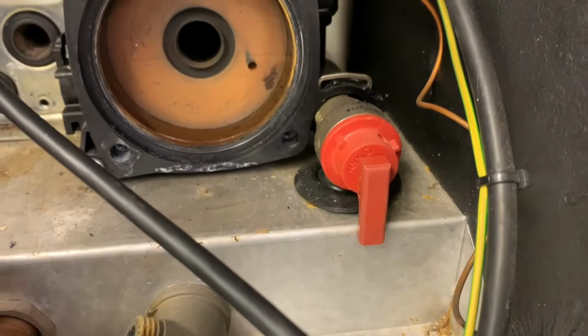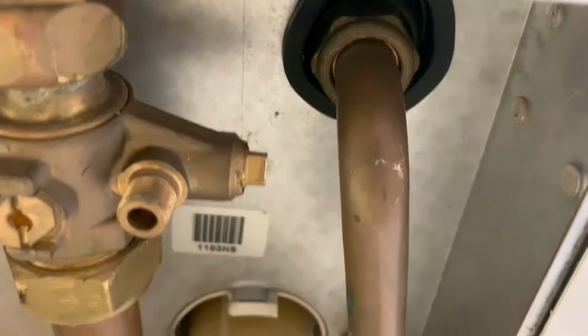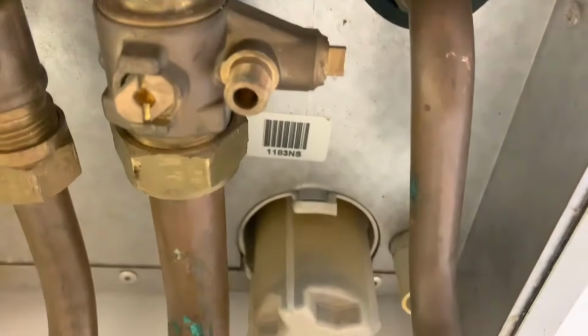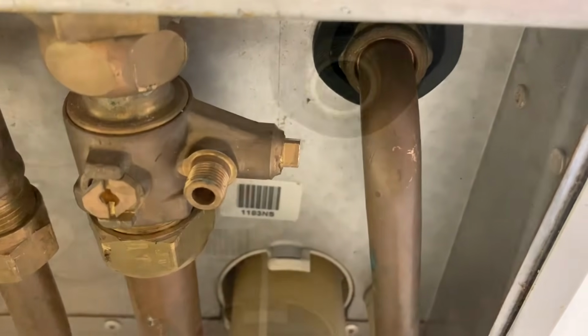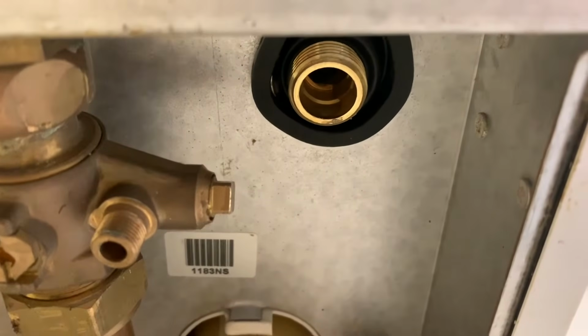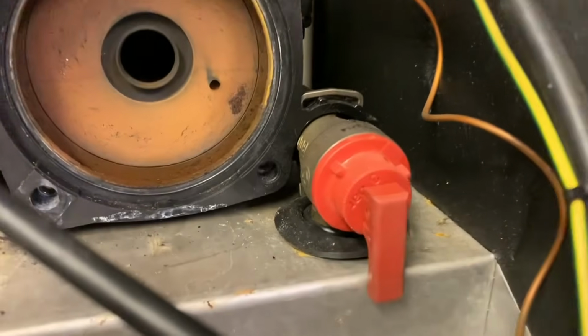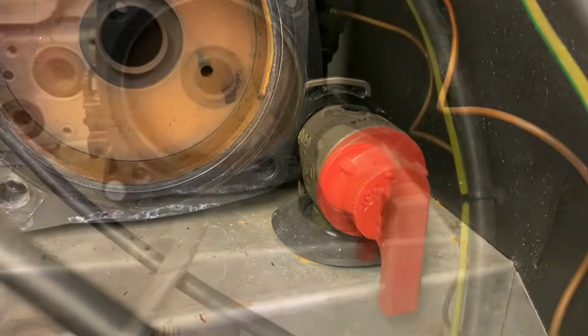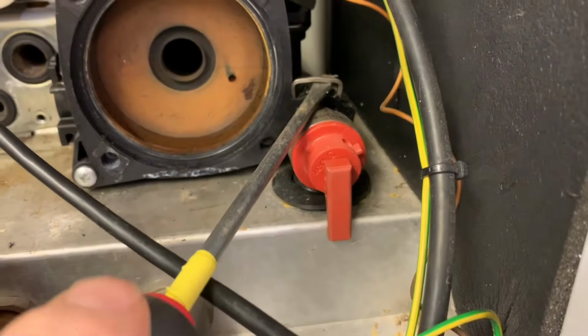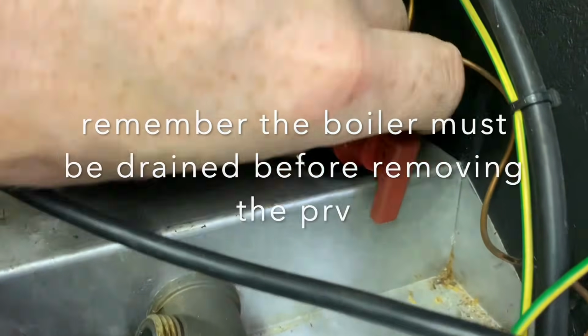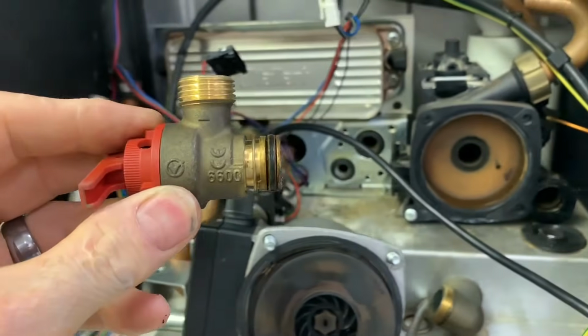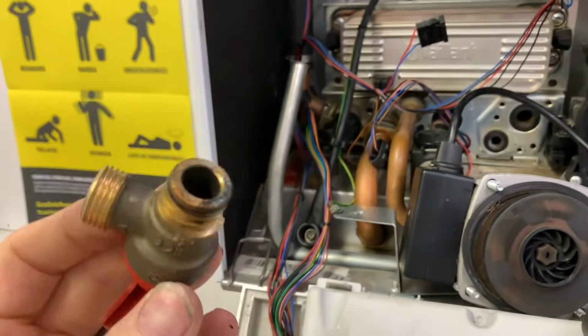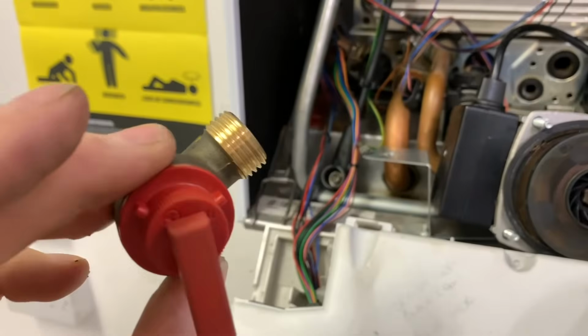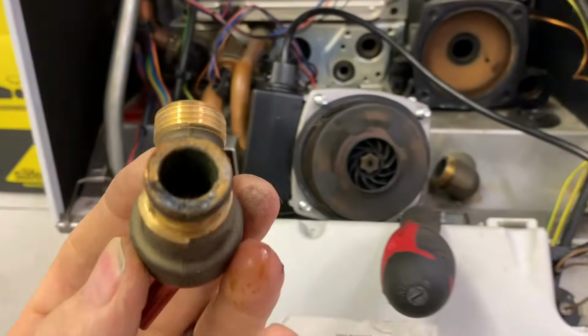Now before we can remove this, first of all we've got to come underneath here and undo this nut to take this piece of pipe off to be able to remove it. Let's do that first. Now the pipe's off, so let's go back up to the top. Let's get a flat screwdriver into that clamp and take that off. Now let's just lift that clamp up, get rid of that. Now this should just pull forward and come out. That's pretty easy. So that is our 3-bar pressure relief valve. Okay, dead easy to change.